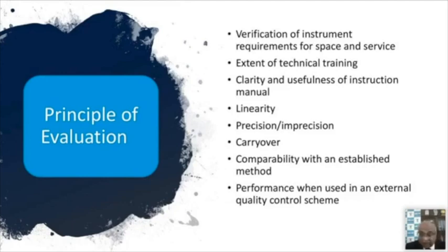Linearity. Linearity is the maximum value which you can report without dilution, or you call it the analytical measurement range also. Precision means how close results are to each other when you are repeating multiple times. Carryover means when you run a high value sample after a low value sample and then run that low value sample again, there is no difference between pre and post high value sample. Your results are not affected by that high value sample in the low value sample. Then comparability with the established method, and we also see performance in EQAS.